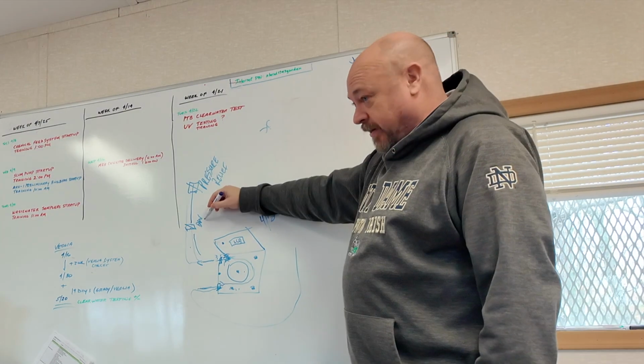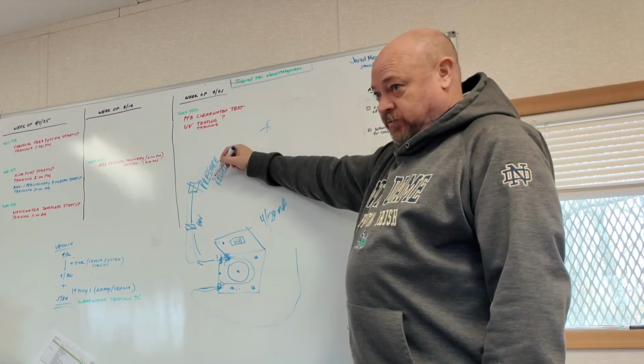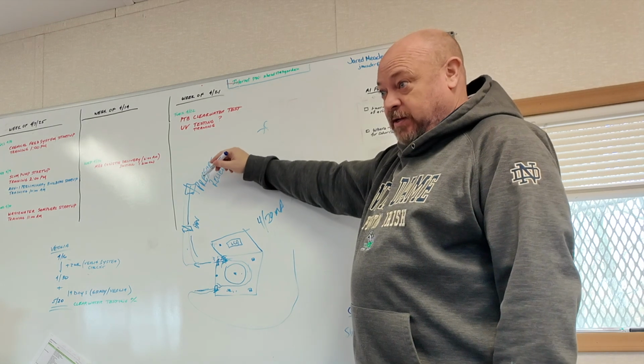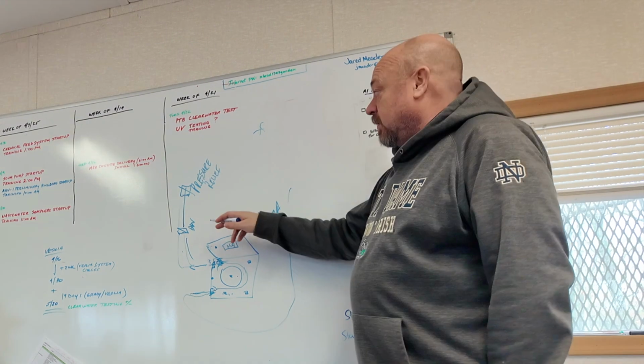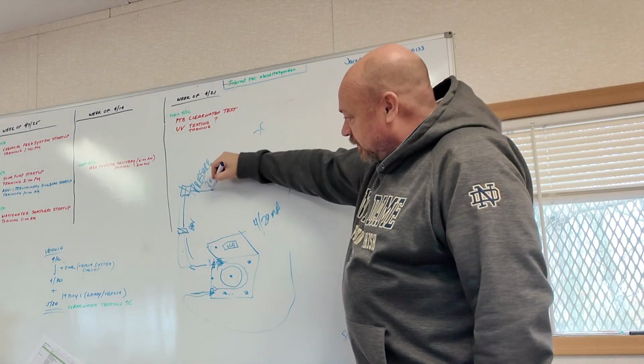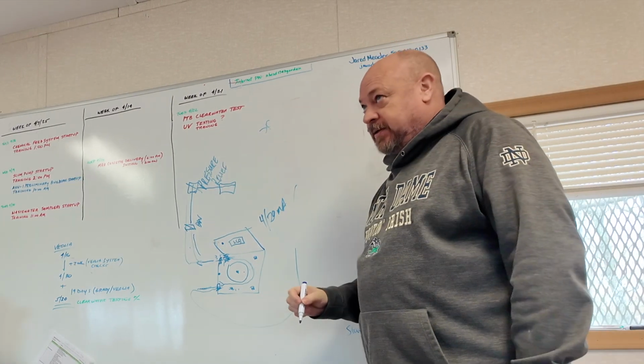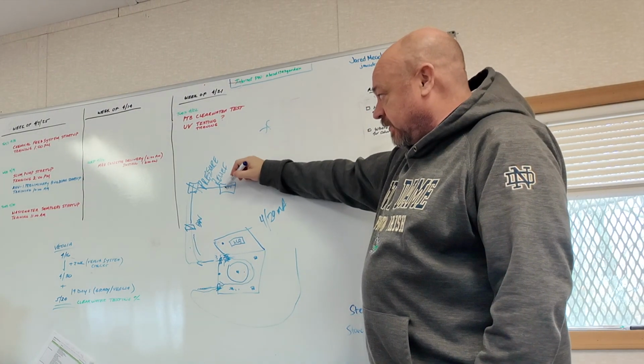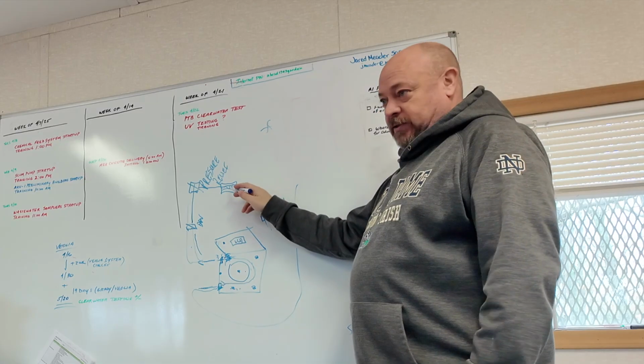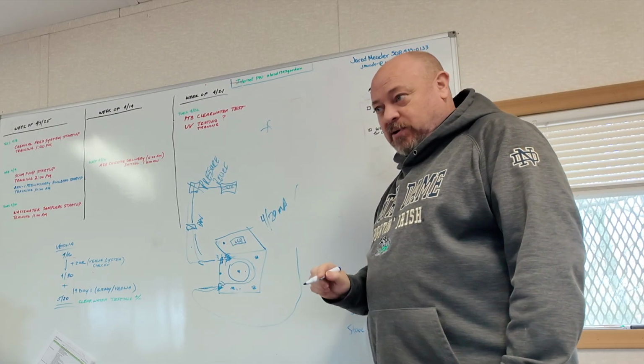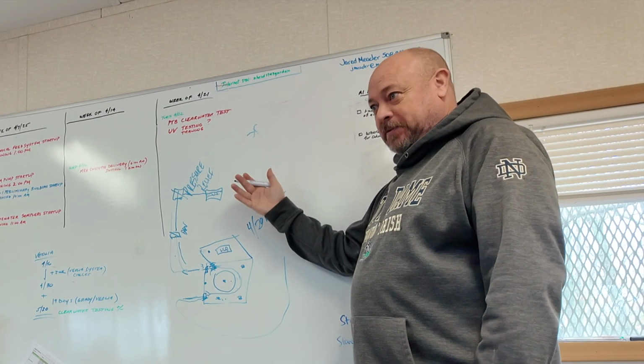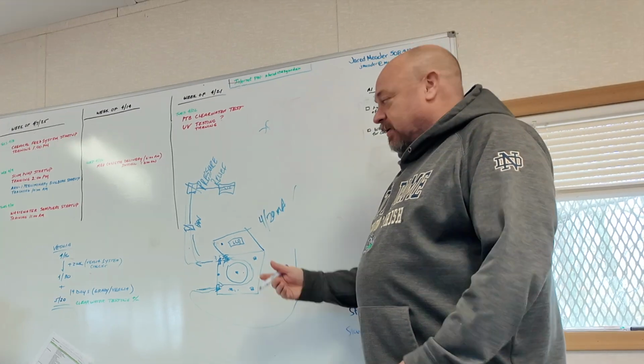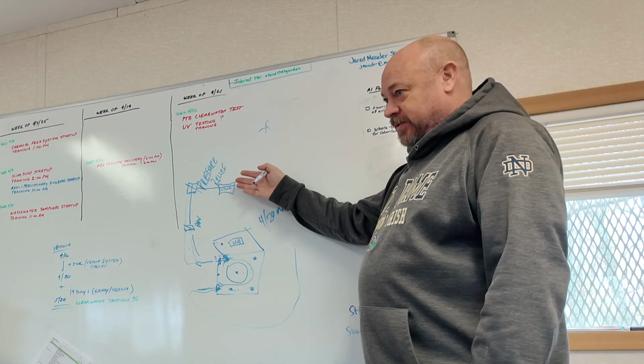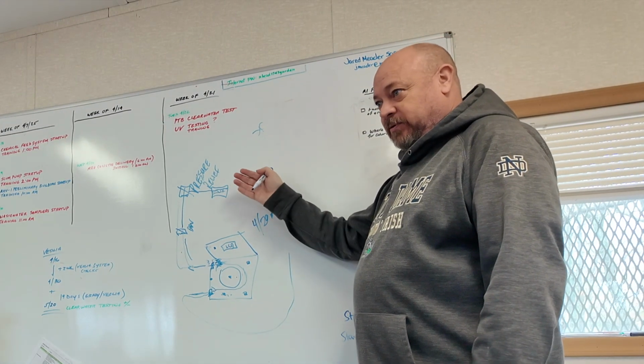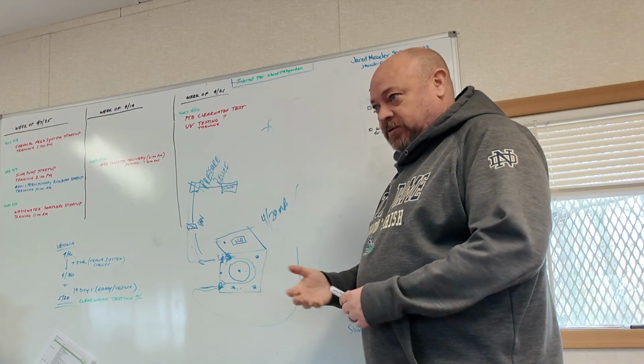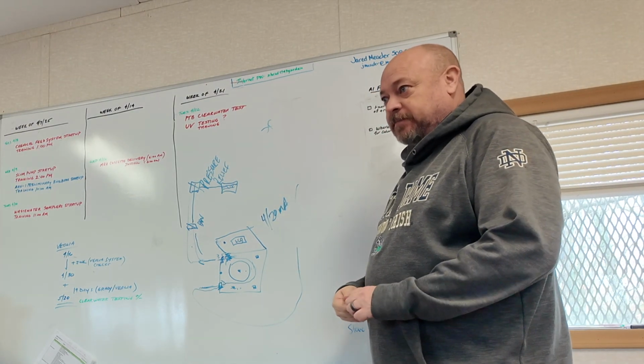So right now, the back pressure valves are set at 30 psi. Pressure reliefs are set at 50 psi. So anything over 50 psi, this valve will open and start to recirculate. On the pump itself, when this relieves, it has a relief line. On 3 of the skid systems, there's a clear sight glass, so you can actually see the product. The downside with this is, depending on the product that you're pumping, you might not be able to tell if it's actually in there because of the opaque color of the glass. If it's sodium hydroxide, you're going to have a hard time seeing it. Citric acid, you'll probably see a little bit of color in it. And the hypo, depending on the strength of the hypo, you'll see a little bit of a tinge of green in it. Micro C, good luck.